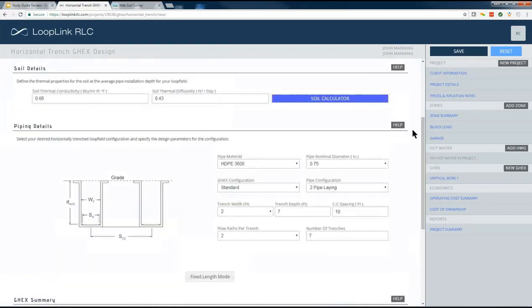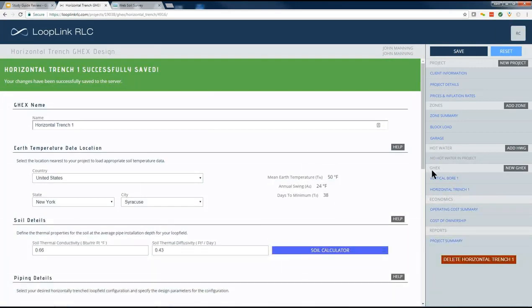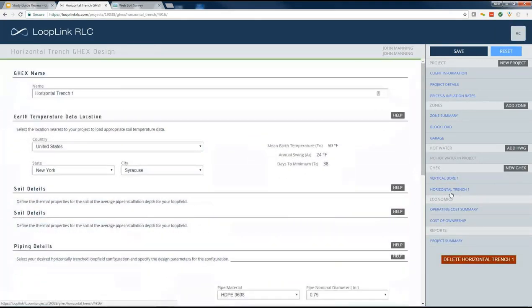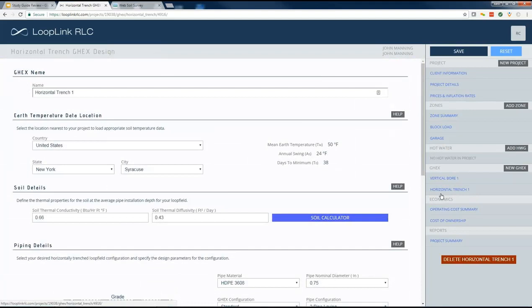Once you're done playing around with this, you can go ahead and save it to the project. Now notice that we've got a vertical bore design and a horizontal trench design loaded up in the project. You can show the homeowner option A and option B. As far as heat transfer and system performance, the only thing your heat pump cares about is how much flow you give it and what the water temperatures are under worst case conditions. So theoretically, both of these loops, the vertical bore and the horizontal trench layout, have been designed to deliver the same performance as far as the heat pump is concerned, ignoring pumping differences, right?